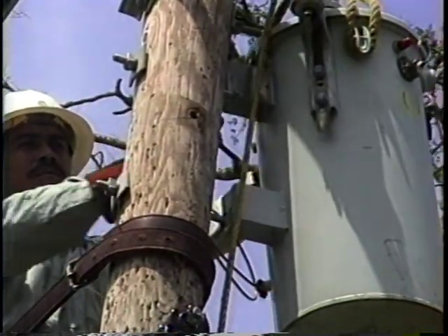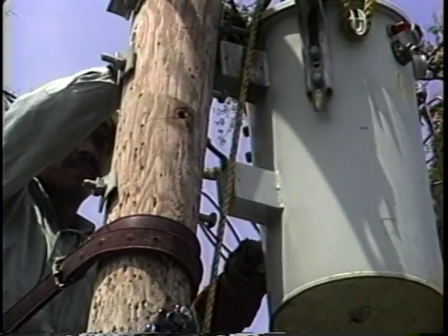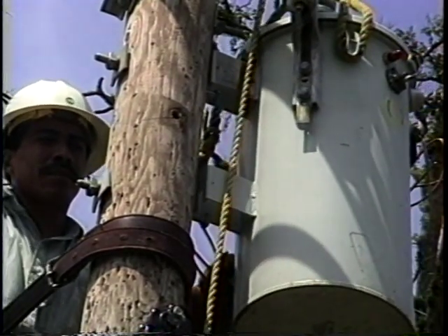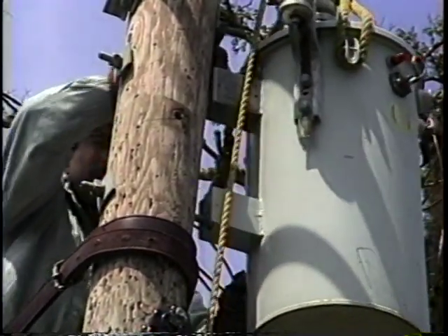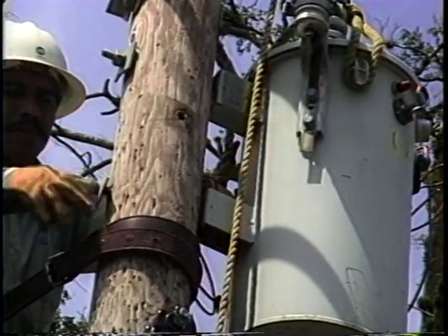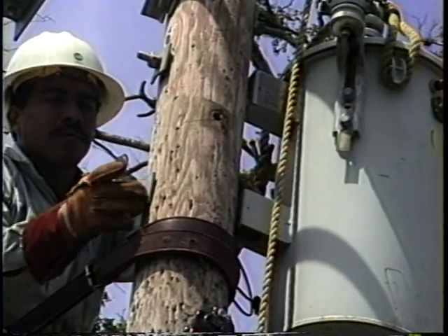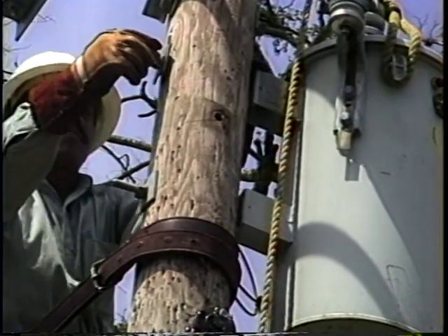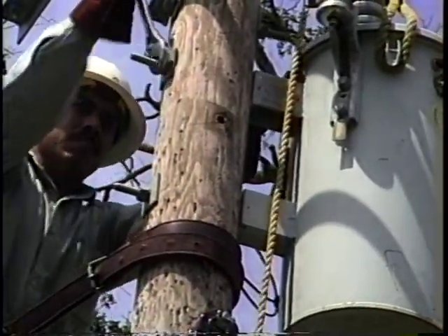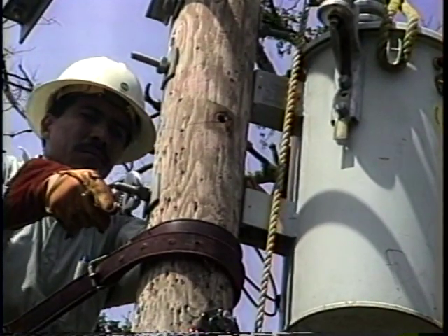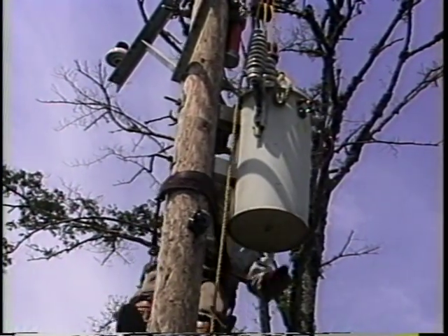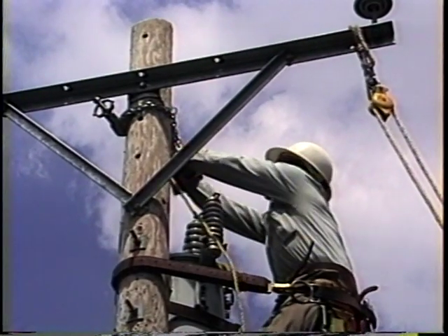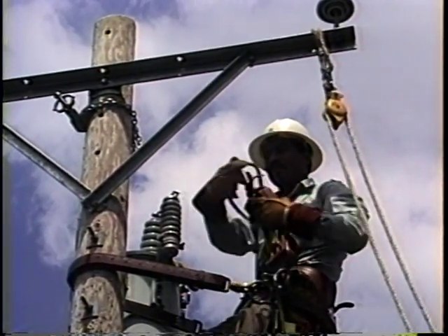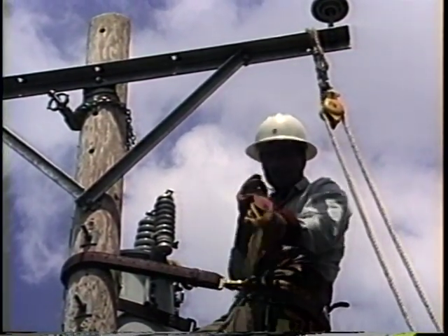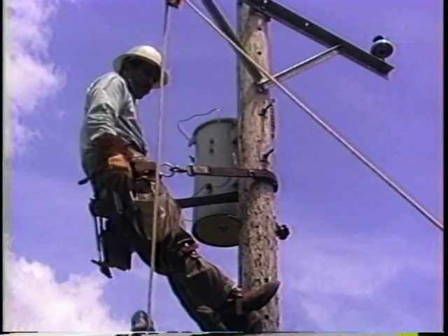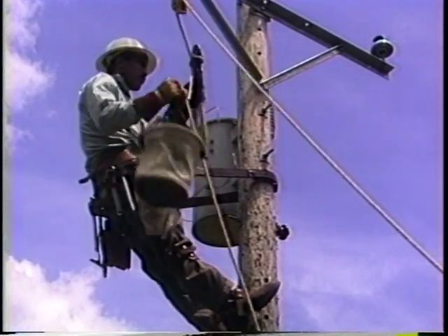Once the transformer's brackets are slightly above the machine bolts, the lineman instructs the groundman to maintain it at that level while he aligns it with the bolts. When the transformer is properly aligned, the lineman instructs the groundman to slowly lower the transformer until it rests securely on the bolts. Tension is maintained until the lineman indicates the bolts have been completely tightened. After inspecting the transformer to ensure proper installation, the block and tackle and transformer gin are lowered. The proper tools and materials required to ground the transformer are then raised.